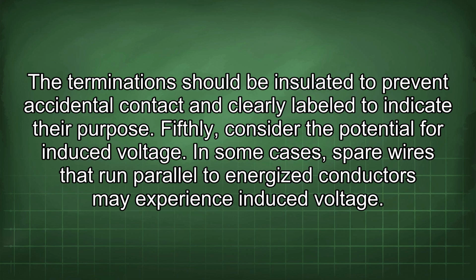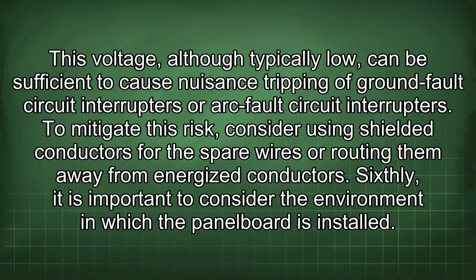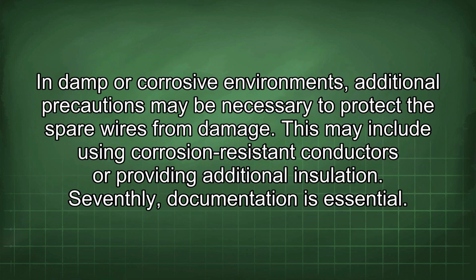Fifthly, consider the potential for induced voltage. In some cases, spare wires that run parallel to energized conductors may experience induced voltage. This voltage, although typically low, can be sufficient to cause nuisance tripping of ground fault circuit interrupters or arc fault circuit interrupters. To mitigate this risk, consider using shielded conductors for the spare wires or routing them away from energized conductors. Sixthly, it is important to consider the environment in which the panel board is installed. In damp or corrosive environments, additional precautions may be necessary to protect the spare wires from damage. This may include using corrosion-resistant conductors or providing additional insulation.